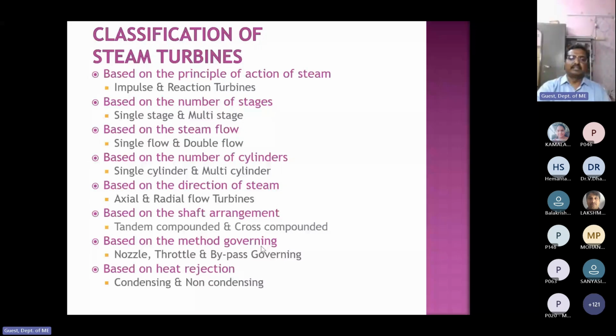All these are done with the same effect, controlling the fuel itself. Here we may not vary the fuel quickly, but we alter the steam inlet to the turbine. By changing the steam inlet, the output is varied. For example, in the evening time, we switch on the lights, all fans, and the load will increase. When the load is increasing, turbine speed comes down.